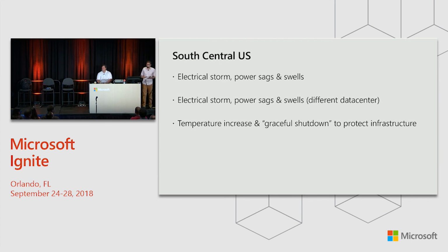So now we're dealing with a situation where staff have been evacuated from the data center. We have to protect lives. The temperature now is increasing at a higher rate than it usually would. And the hardware shutdown didn't occur as rapidly as it should have in some areas, and we received damage to storage, a critical part of storage and some of our networking infrastructure in that area.